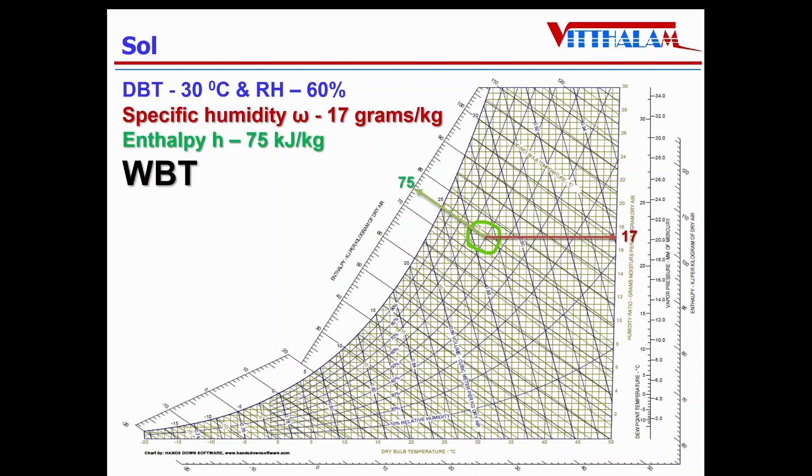Third property is the WBT, wet bulb temperature, which is also an inclined line. And when I draw inclined line and it intersects the saturation curve, the value on the saturation curve on WBT, in this case it is 24.8 degrees Celsius.